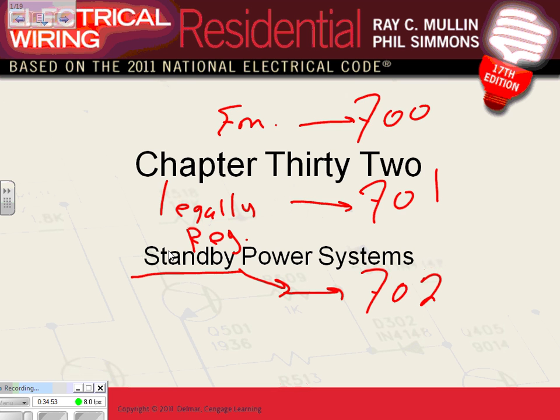The emergency system, by code, has to come up within 10 seconds. The legally required standby system has to come up within, anybody know? What's the time that the equipment has to come up within for a legally required standby system? 60 seconds. And all this information is from Article 701, guys. And how about the standby system? How long do you want it to take to come up? Whenever. I always say, whenever Chad finishes his cup of coffee and goes to turn the switch on. Okay, three very important systems: 700, 701, 702.